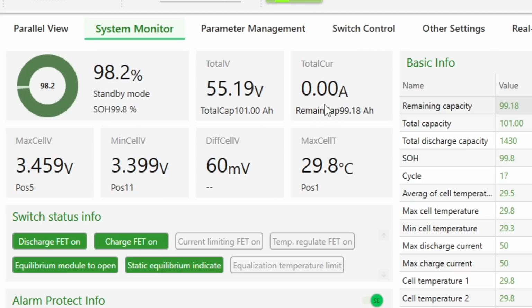So officially we are not charging anymore. This would actually meet condition number 1 now, but we are not at 55.2 volts. The voltage is just 10 or 20 millivolts lower than the requested charge voltage. So neither condition 1 nor condition 2 is met now, and none of the timers is running, so the BMS will not reset to 100%.